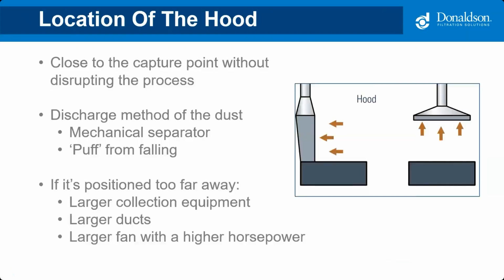To minimize air volume, the hood must be close enough to the capture point without disrupting the process. We only want to collect fugitive dust and not good product. A hood positioned twice the design distance from the contaminant emission point will need to draw approximately 4 times more air to produce the same capture efficiency. This is why proper design is critical, because more air means larger collection equipment, larger ducts, larger fan, higher horsepower, all of which add capital and operational costs.